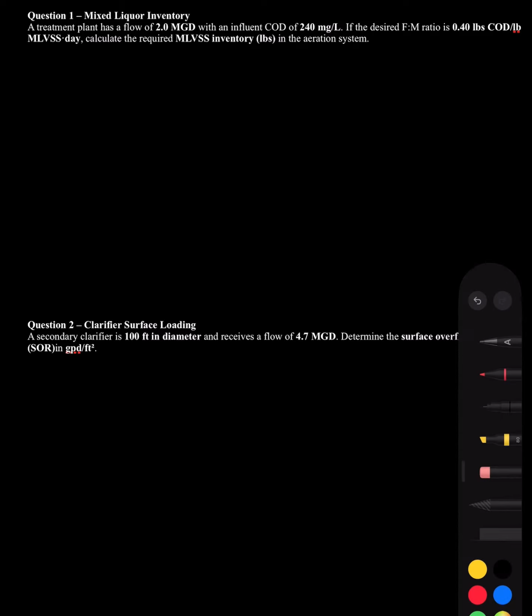Question one today is on mixed liquor inventory. It says a treatment plant has a flow of 2.0 mgd with an influent COD of 240 mg/L. If the desired F/M ratio is 0.4 pounds of COD per pound of MLVSS per day, calculate the MLVSS inventory in pounds in the aeration system.